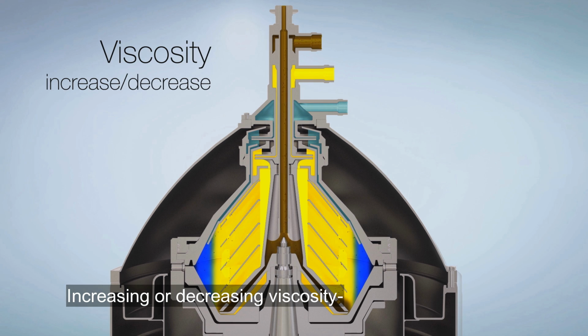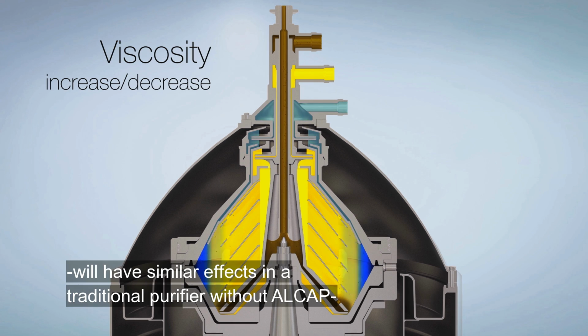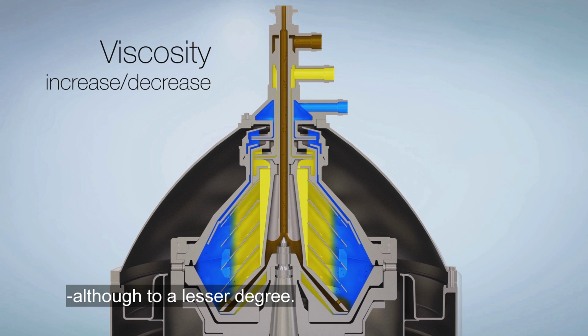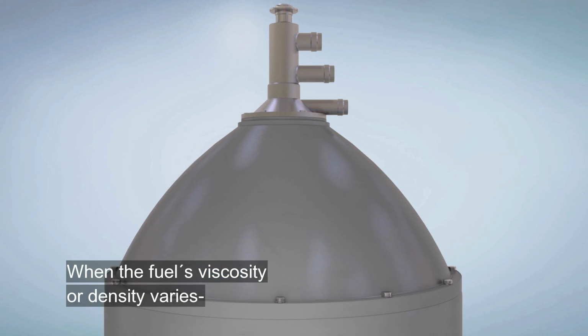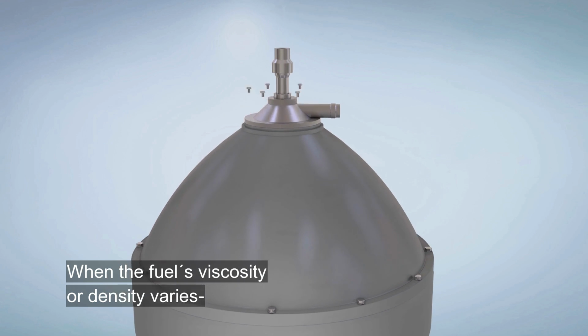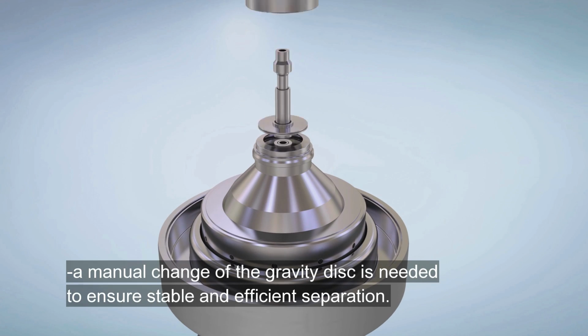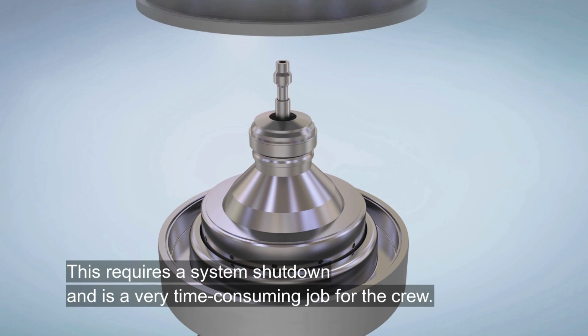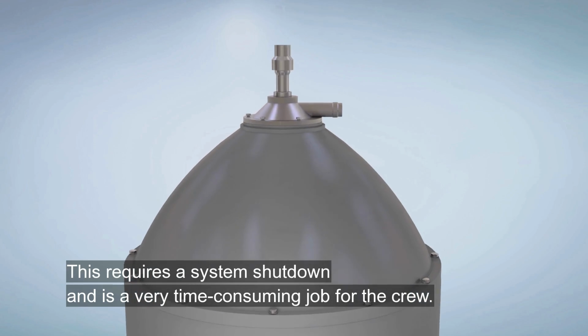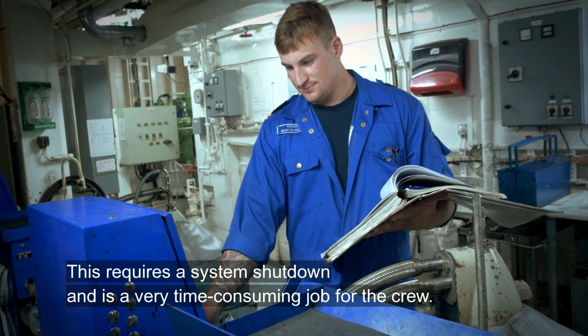Increasing or decreasing viscosity will have similar effects in a traditional purifier without Alcap, although to a lesser degree. When the fuel's viscosity or density varies, a manual change of the gravity disc is needed to ensure stable and efficient separation. This requires a system shutdown and is a very time-consuming job for the crew.